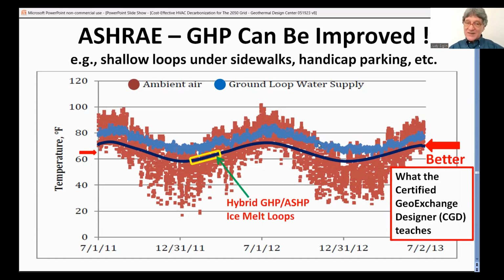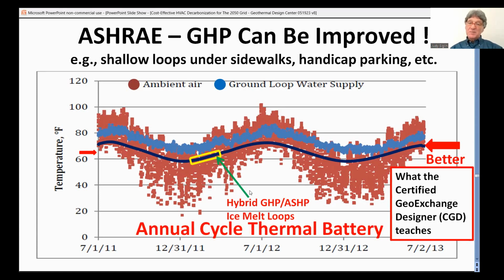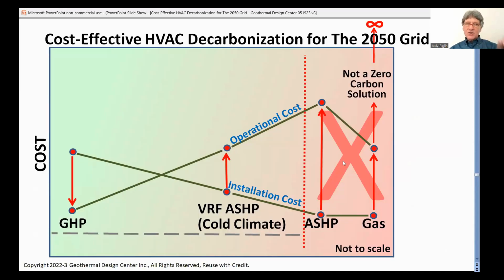And there are ways that you do this. You tune it by wasting heat out of the system in the spring when it's very cool in the evenings and the power is very cheap. So there's specific ways you do this that are known by people in the field, not known by others. You put in maybe ice melt loops under your sidewalks and parking lot areas, and you just use those in the spring to waste energy, or when there's snow and ice. It's an annual cycle thermal battery — that's the key point. This thing varies annually with its load, this big chunk of earth under a building.